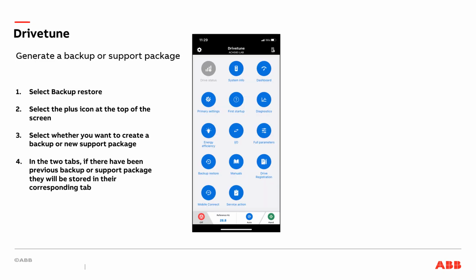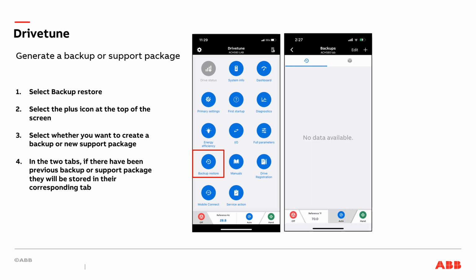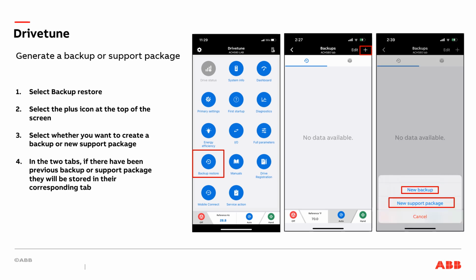Now that we have Drivetune connected to the control panel of the ACH580 drive, we will select the Backup and Restore button on the mobile device screen. After making this selection, you'll notice that the next screen has 2 tabs. The tab to the left is for backup files. The tab to the right is for support packages generated by using this device with Drivetune. To create a new backup or new support package, select the plus symbol at the top right corner of the screen. You will then select one of the 2 options.